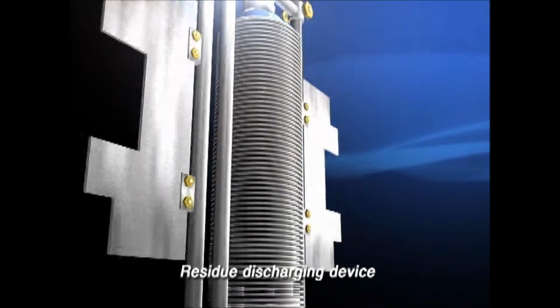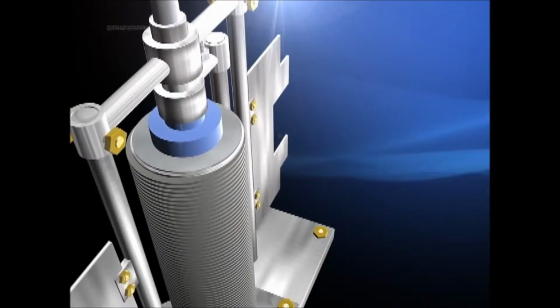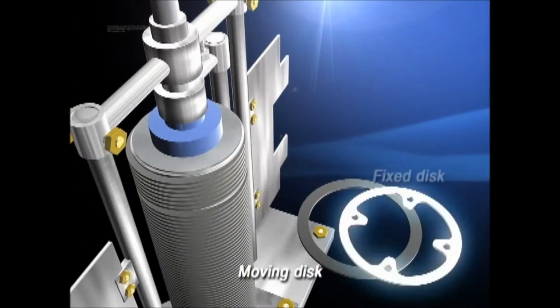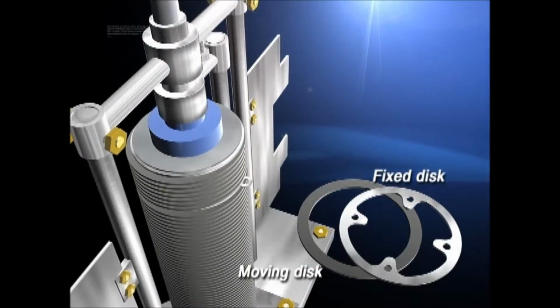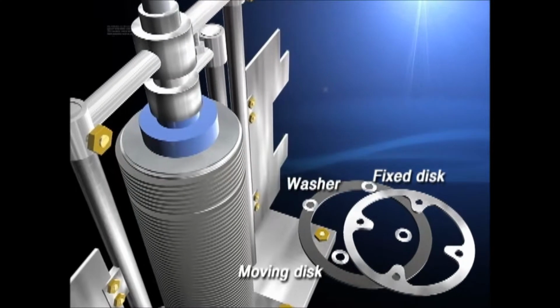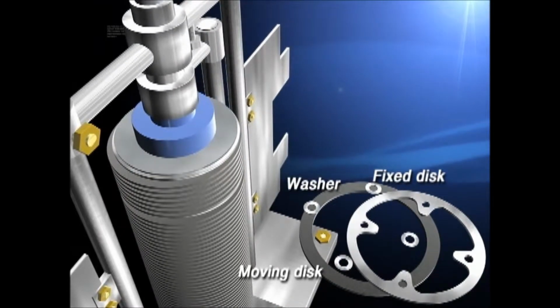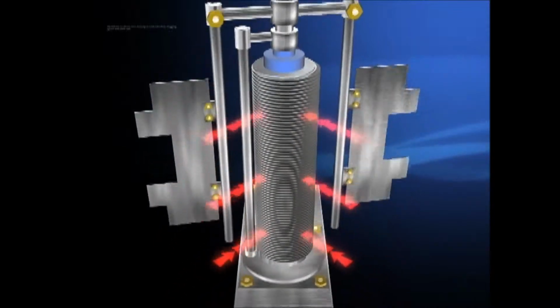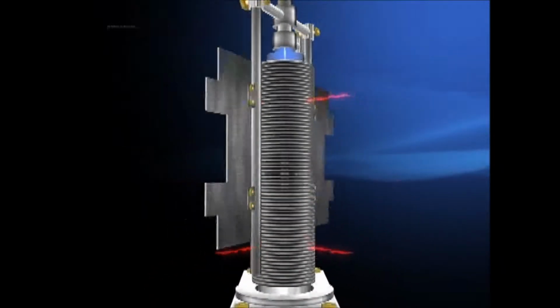The residue discharging device used to discharge the residue liquid from the formed flock is composed of a moving disc and a fixed disc, driven by a scraper. Washers are placed in between these discs to ensure a regular gap. As a result, an aperture is formed and discharges the residue liquid in the middle of the concentration process.